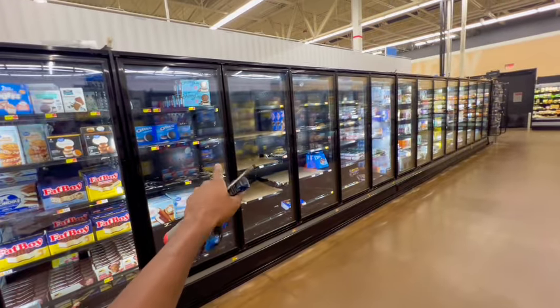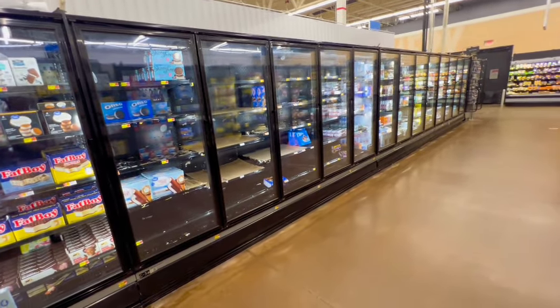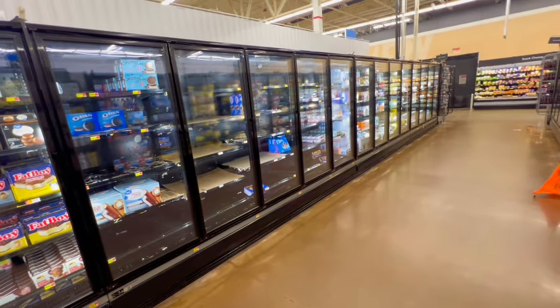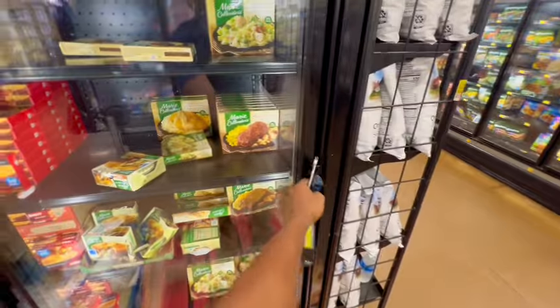This case right here constantly stays down, constantly. It keeps freezing up. I don't know how many folks have been on this case, but it constantly freezes over every time. All right, guys, these other set of cases, they got good airflow across. This one, about 8 degrees.